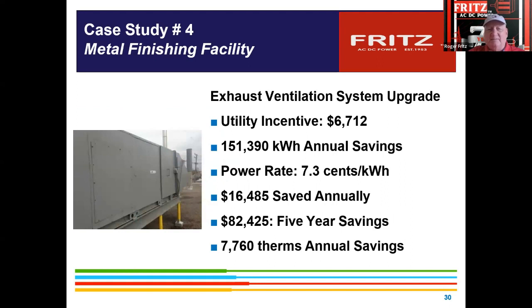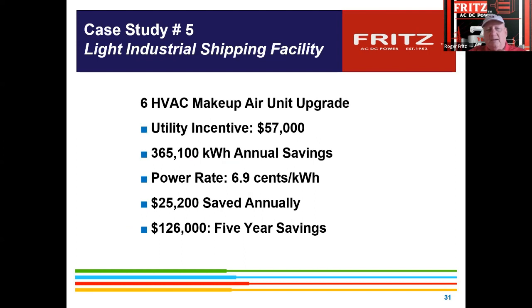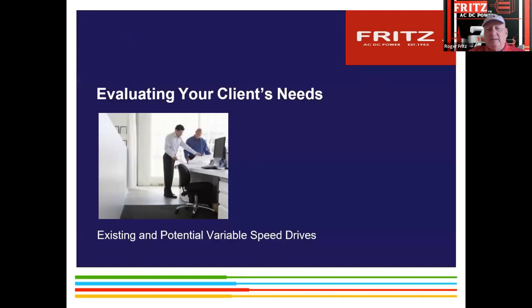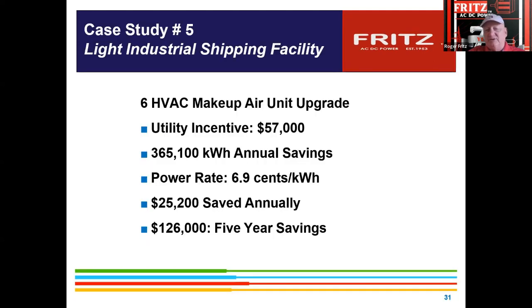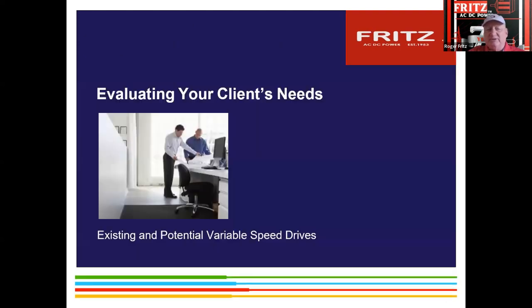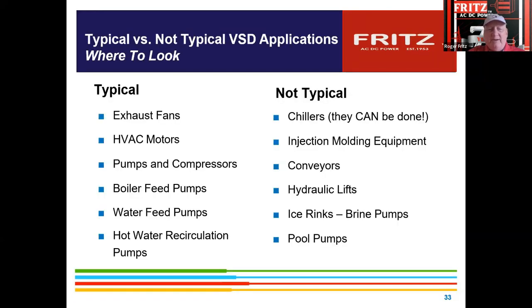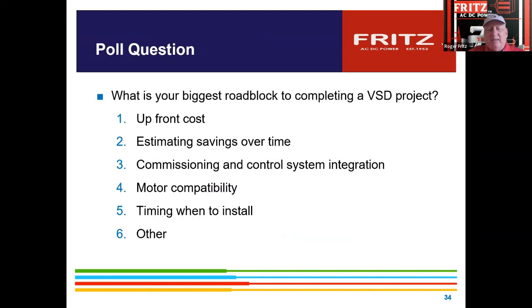Exhaust fans, ventilation upgrades, makeup air, again upgrading those. And these happen to be in some Midwest locations where the utility rate was much cheaper than in some of the coastal locations. What to do when you're going out and evaluating: you want to look even deeper at the non-typical, because there may or may not be incentives on those.